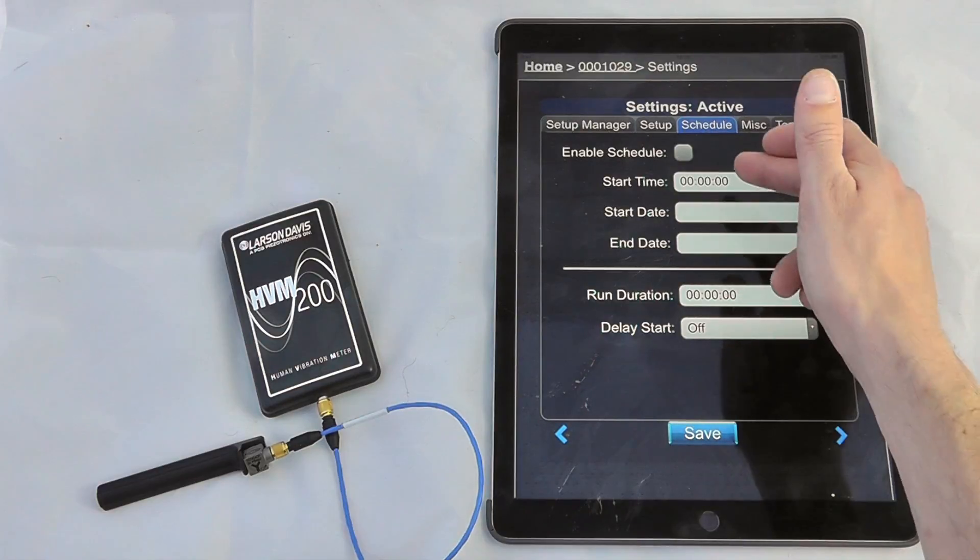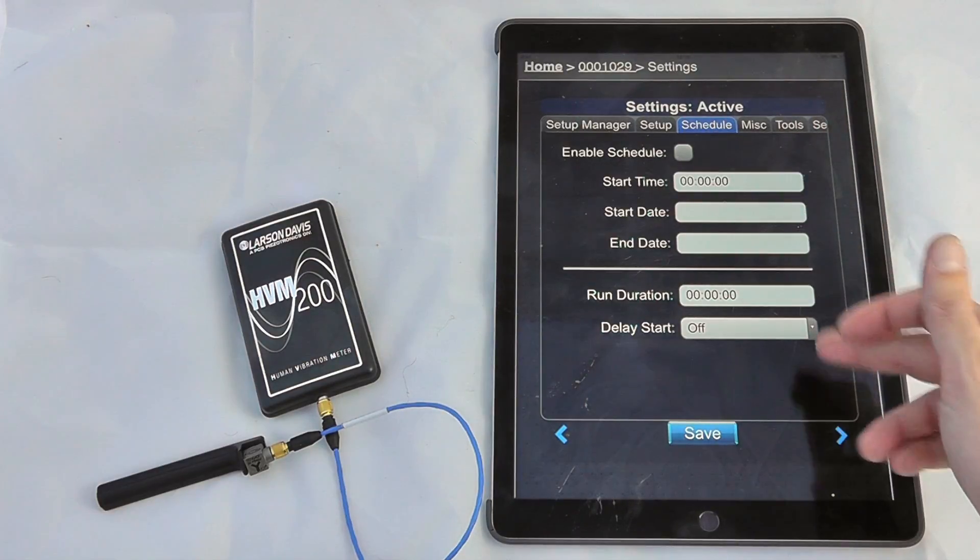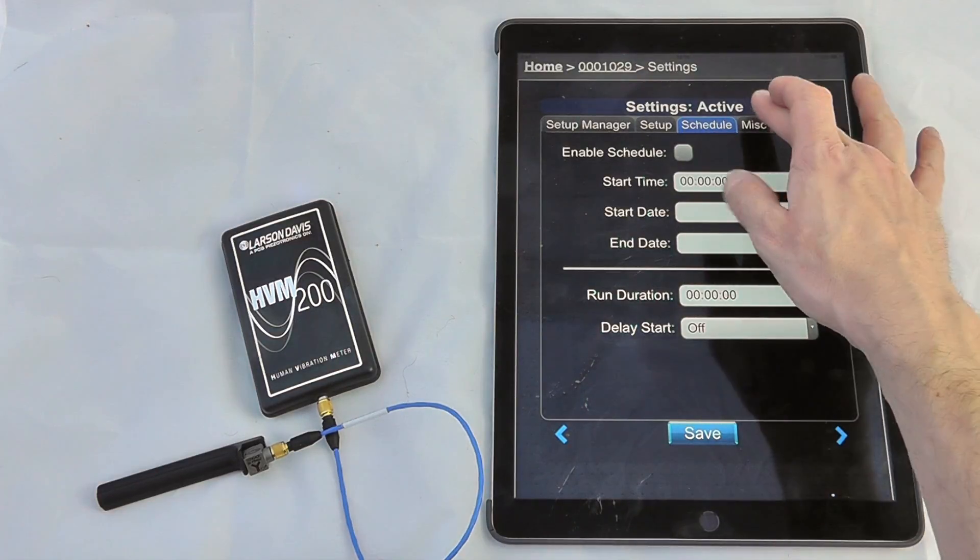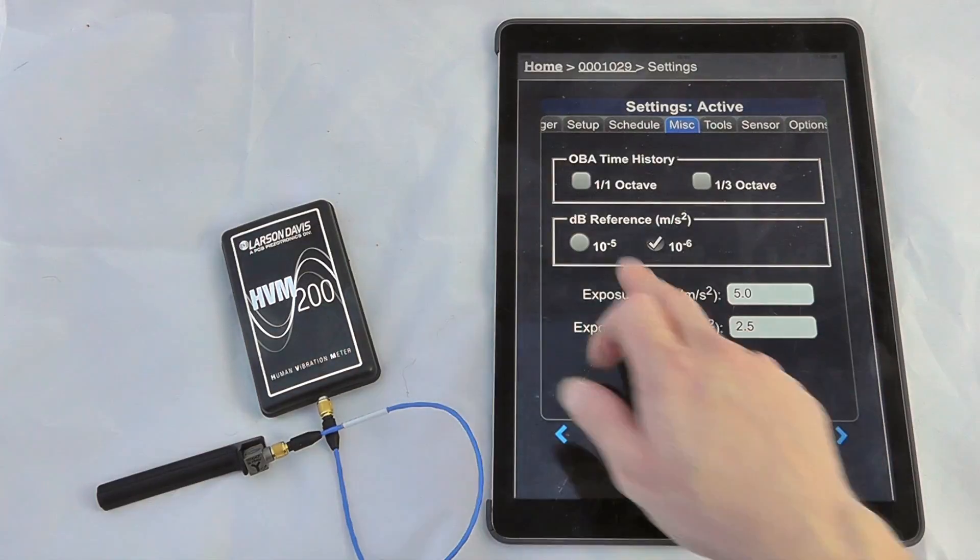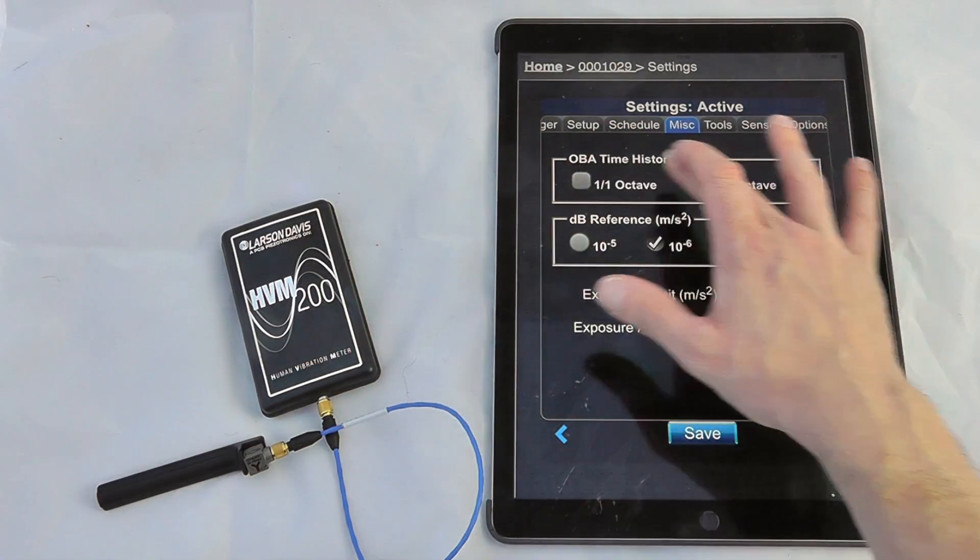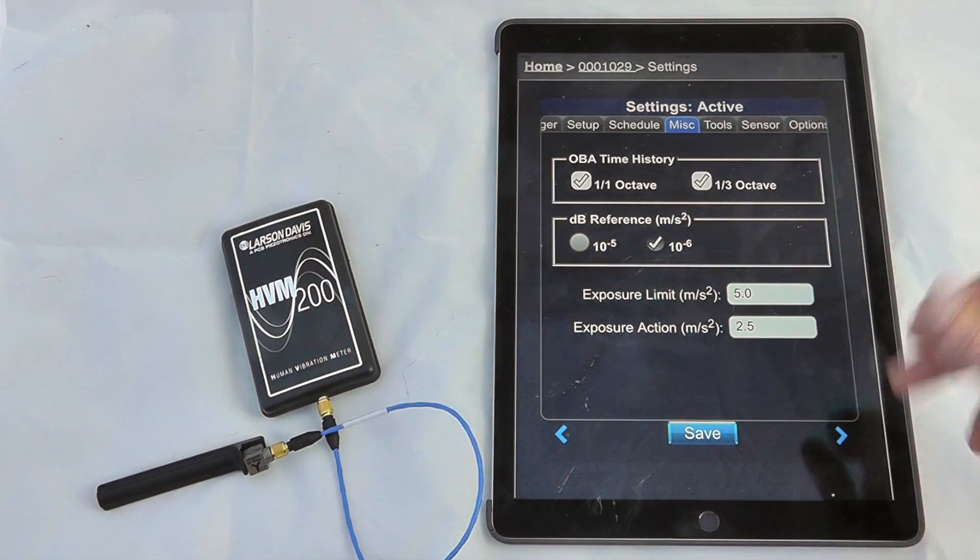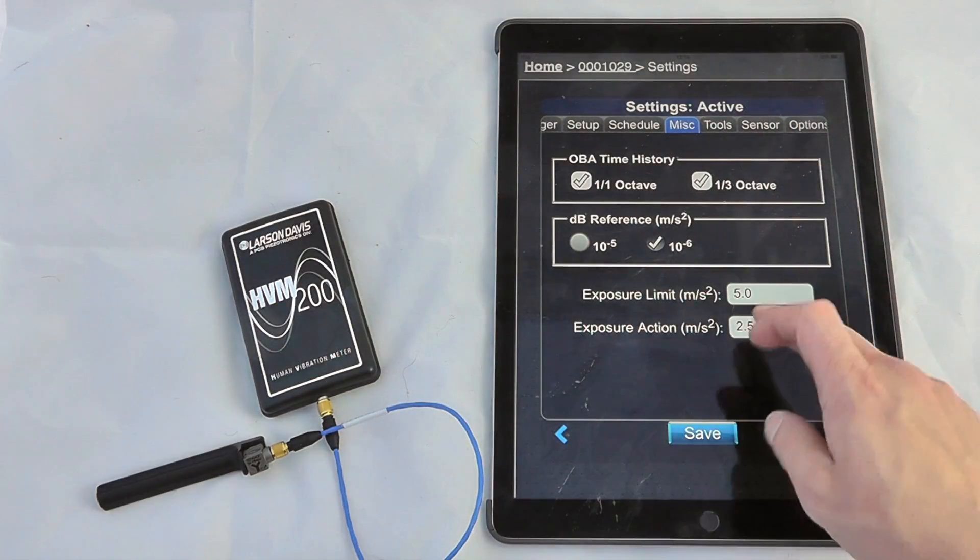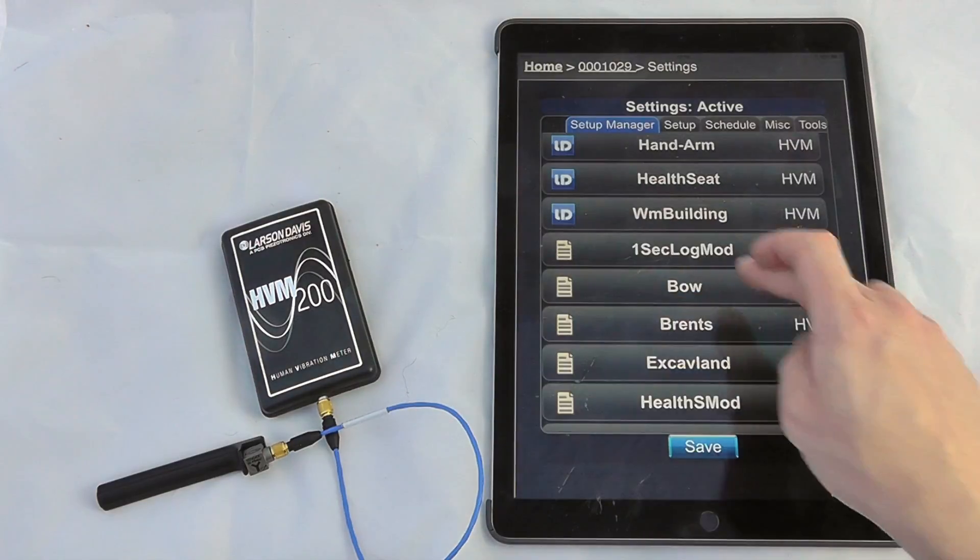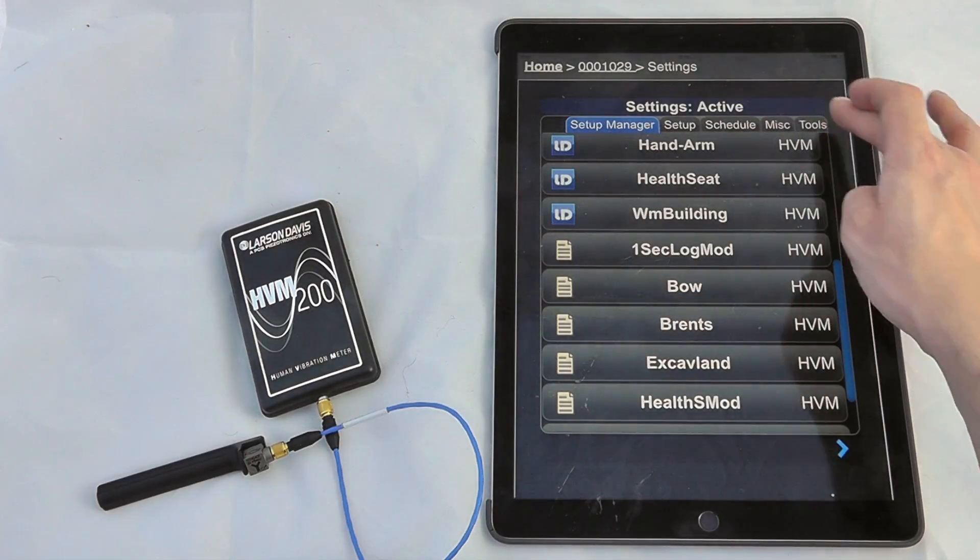We can enable a scheduled start and stop time for the instrument and what the run duration might be. Any miscellaneous settings like adding octave band history, so I will enable octaves and third octaves on this device just so we can show you what we've got there, and save that setting. Yes, I would like to apply those changes.